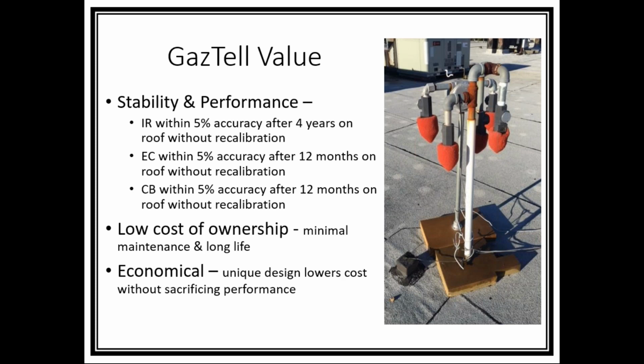Low cost of ownership, another high value reason why. It's minimum maintenance and long life. I know Hugh Avery's on the phone. Hugh had done an example of the cost of ownership of the infrared versus a competitive unit that was out there that needed to be calibrated every 30 days. And it was in the thousands of dollars after 4 years to do 8 sensors. So Hugh was able to win that program quite easily, showing him the lower cost of ownership of the Delphian infrared technology.